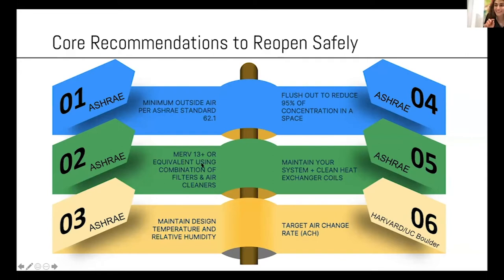The equivalent here is key. For example, a lot of our clients have double stage filtration, like a MERV 7 and MERV 11, or MERV 7 and MERV 10. If you have double stage filtration, you don't need to upgrade each filter to MERV 13. You might get away with it if you can prove that the combination of filters is equivalent to MERV 13.